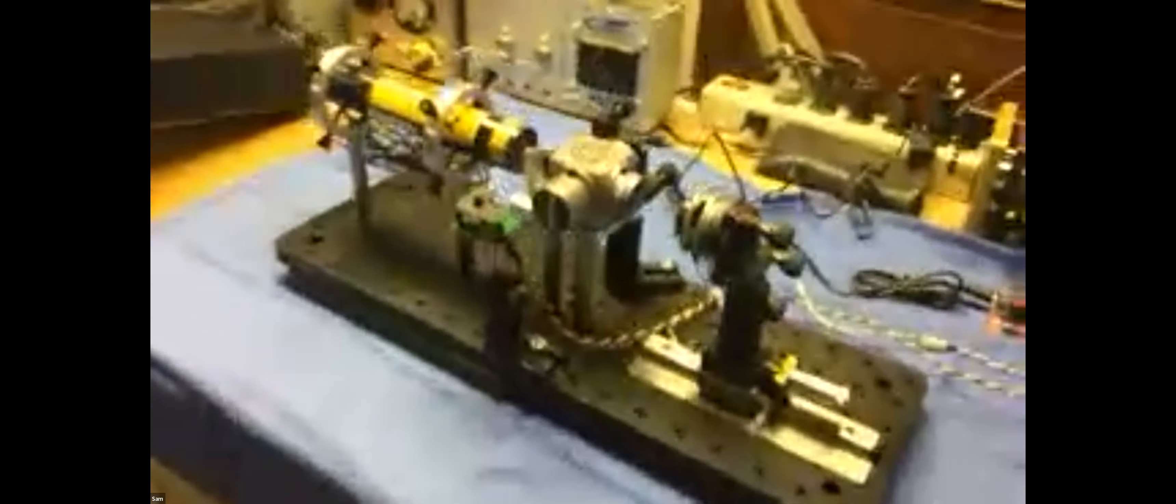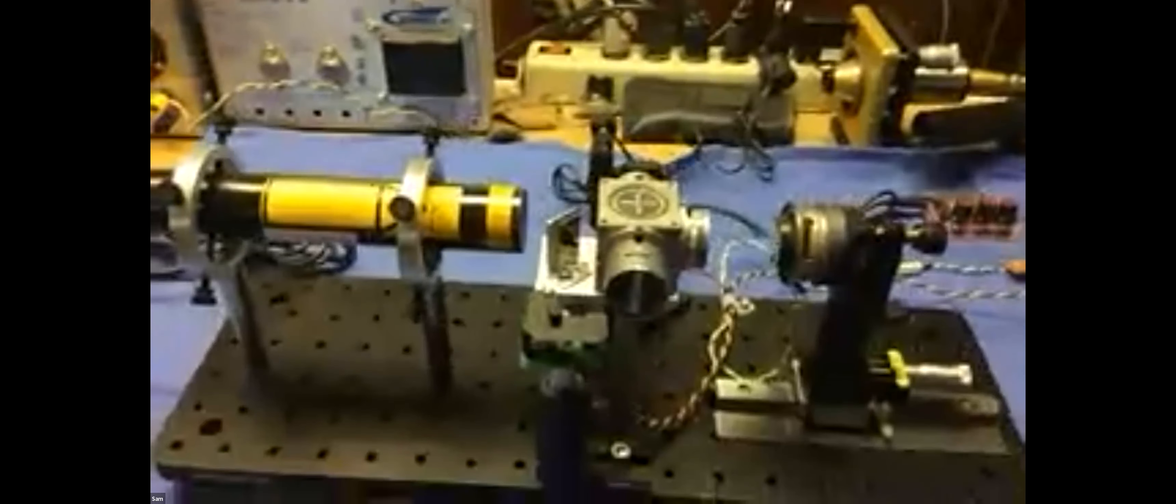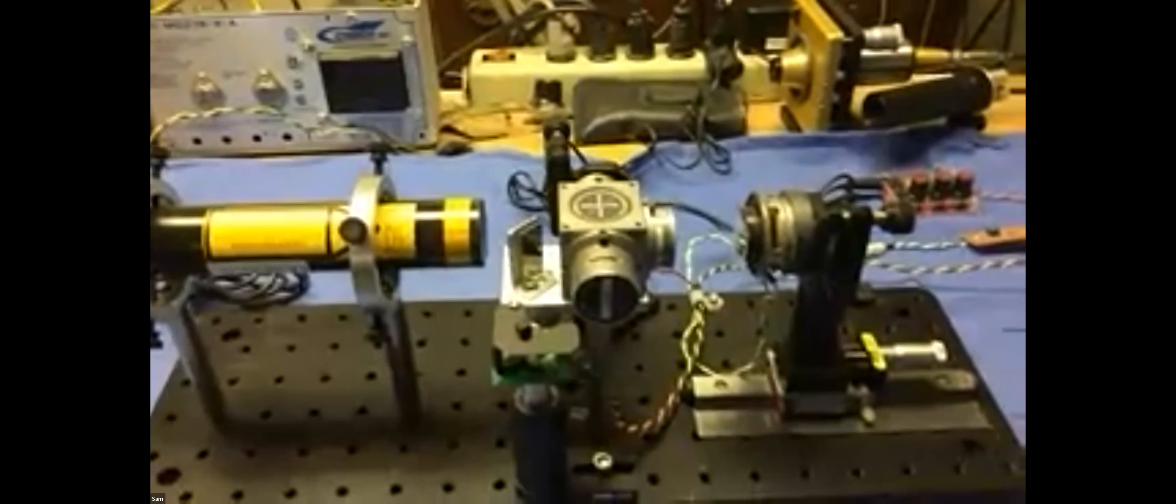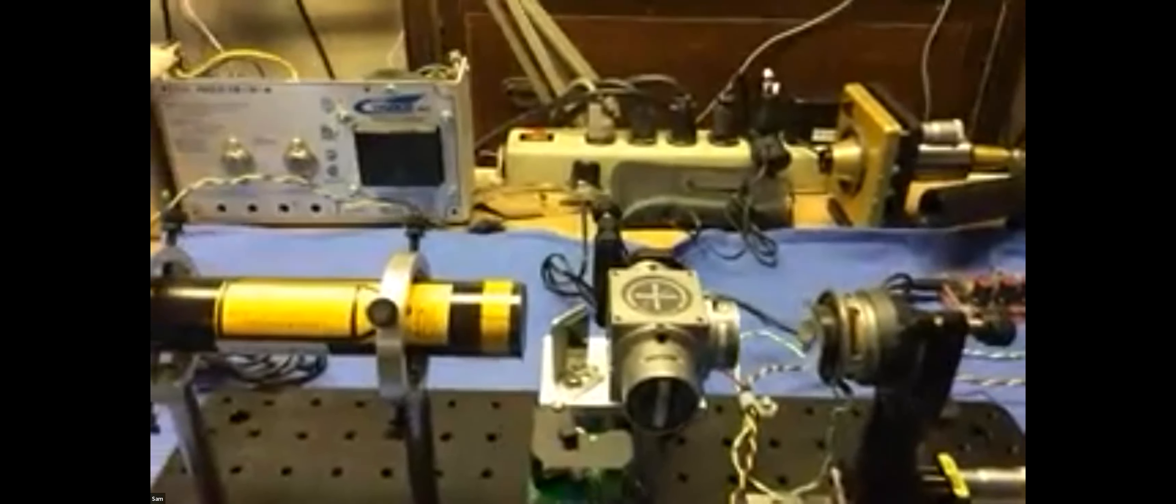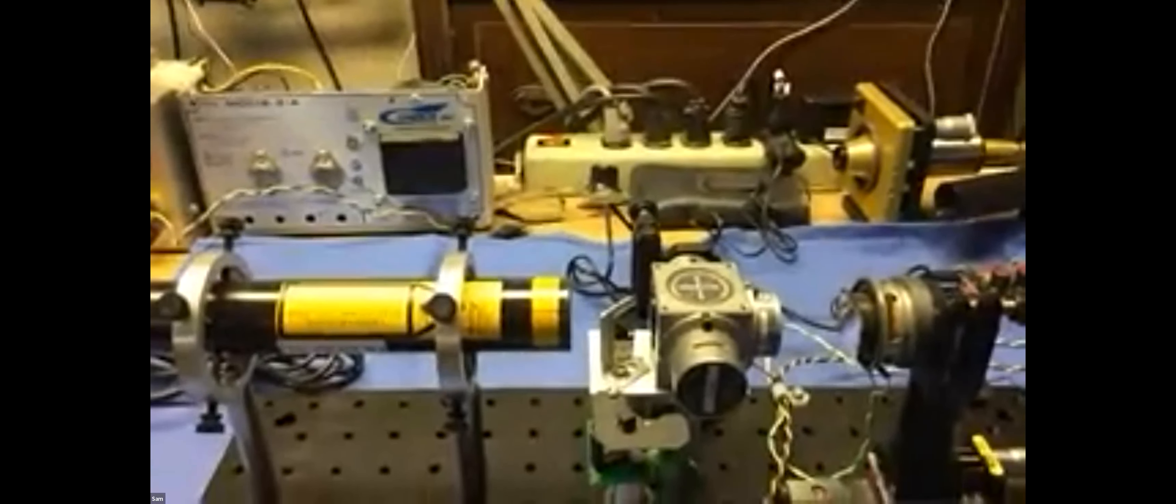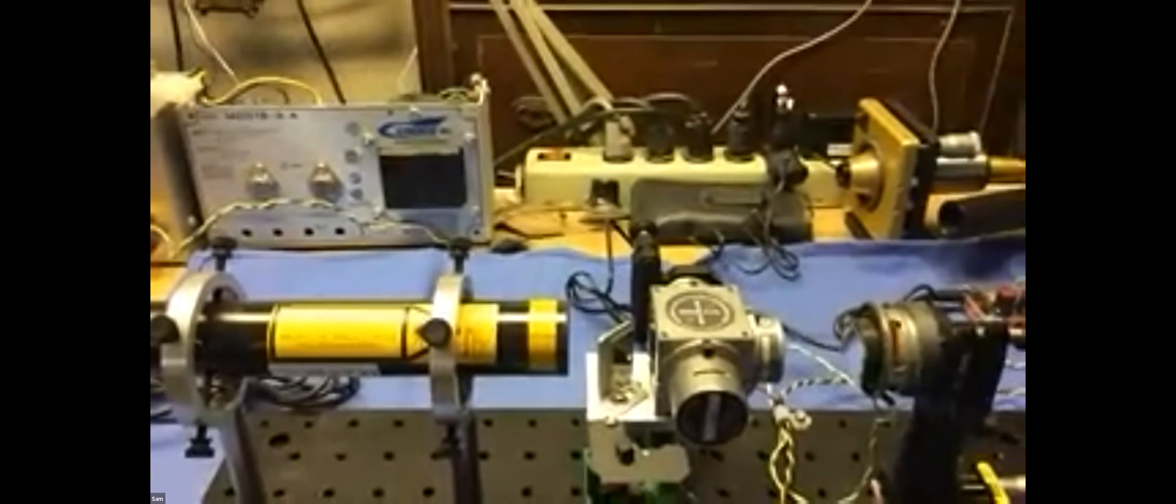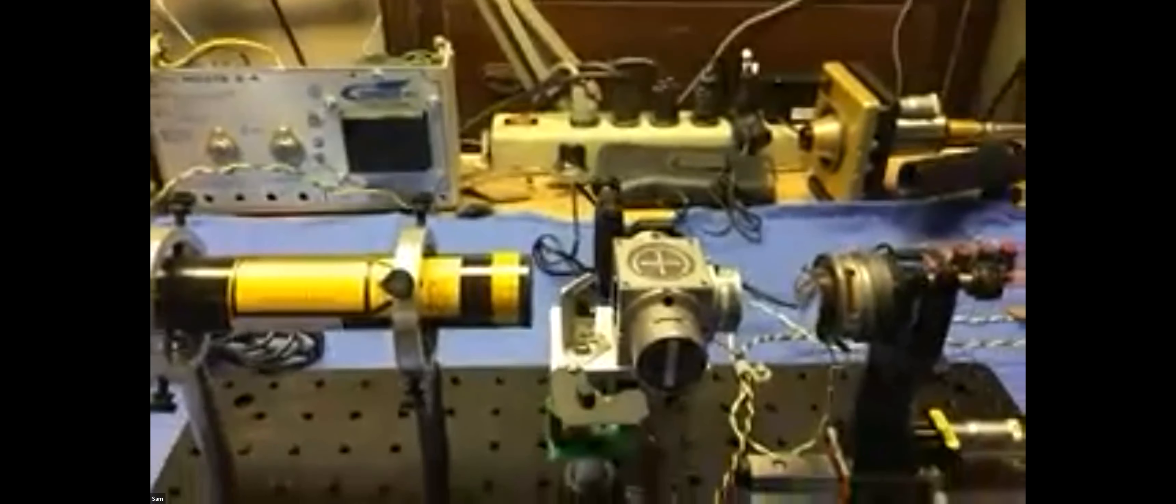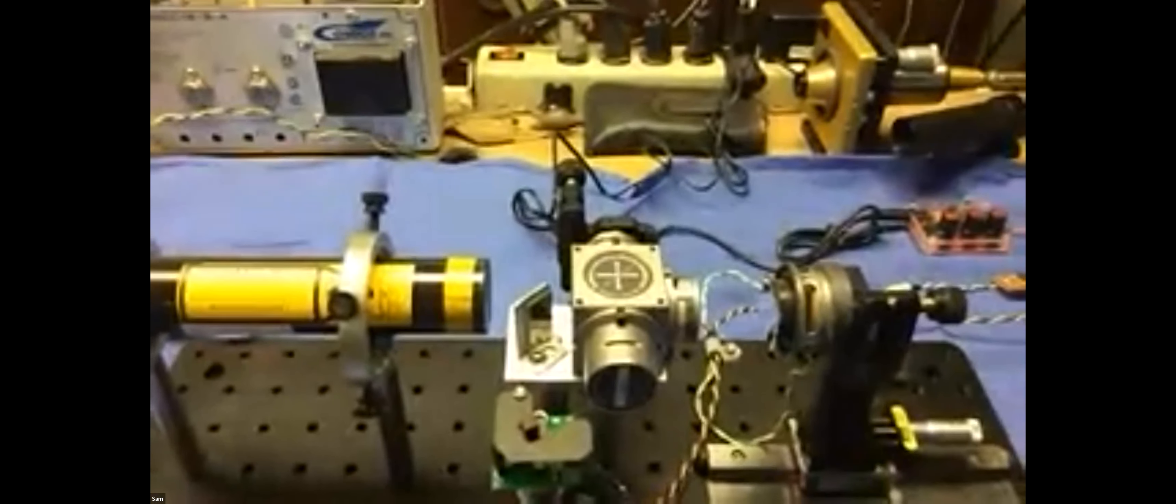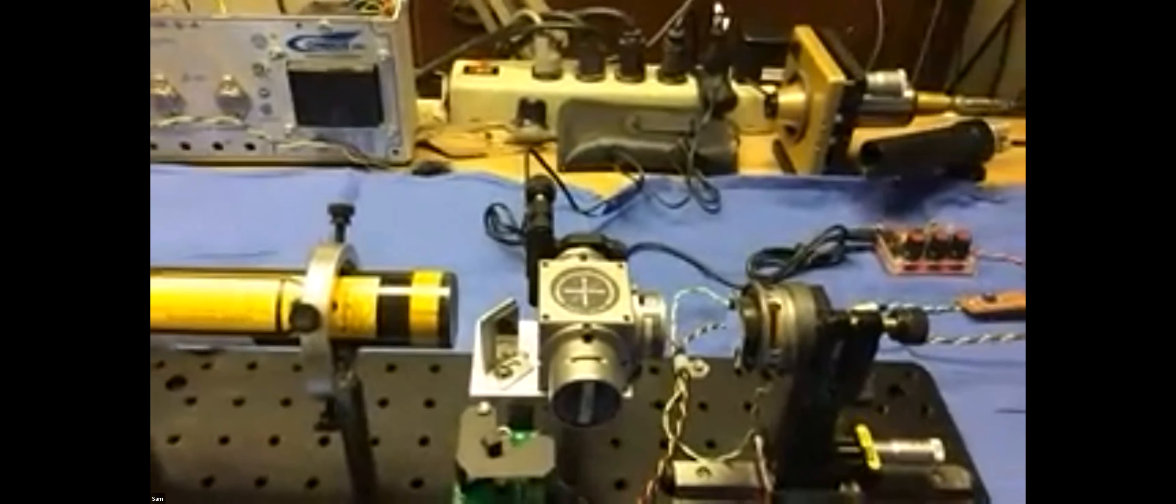You said one rotation is 158 nanometers? Yeah, this is the high-stability plane mirror interferometer so it has double the resolution of the modified linear interferometer, which is what you'll be using. And the reason is that it uses plane mirrors instead of the cube corners, and when you use plane mirrors the light goes two times through the interferometer cube. The way the quarter wave plates change the paths is that it ends up going through the cube twice as many times, so there's double the path length and double the sensitivity.